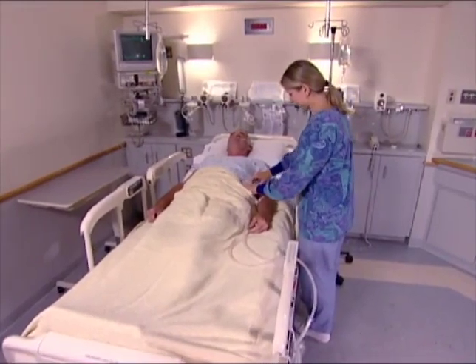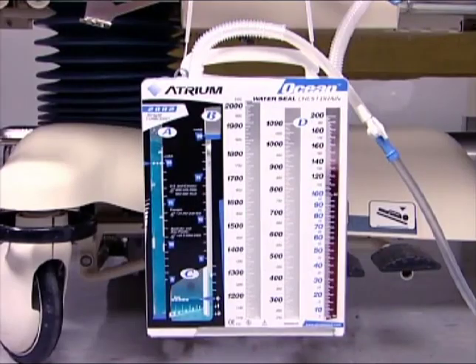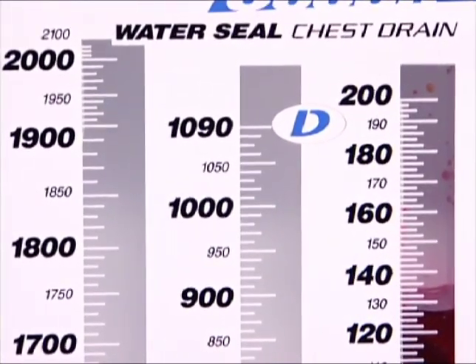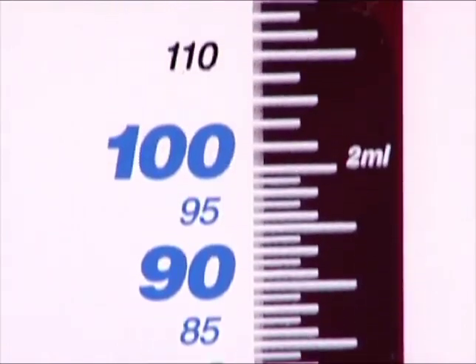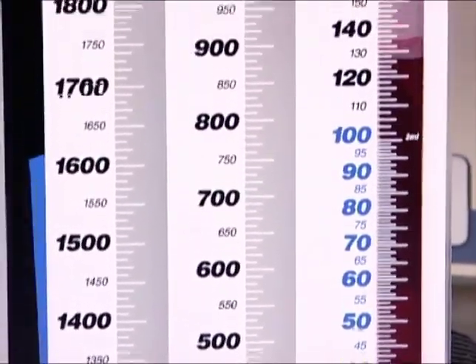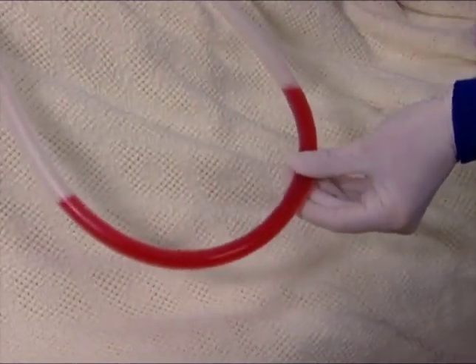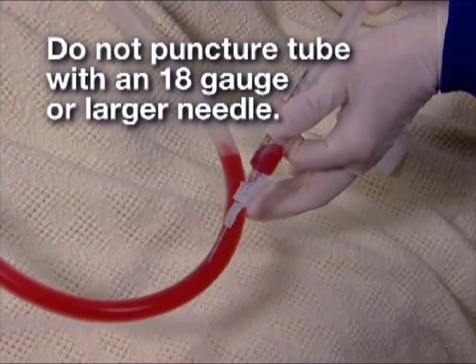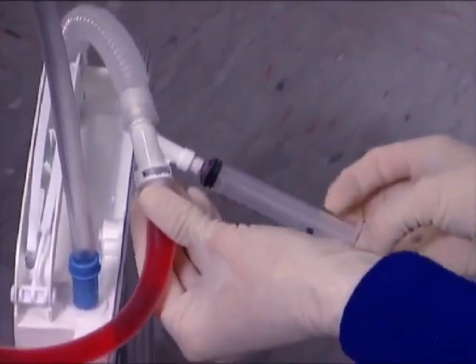All patient tubes and suction connections should be routinely checked to ensure proper leak-proof operation and chest tube patency. The Ocean 2002 Single Drain Collection Chamber incorporates a large writing surface with big, bold numbers and easy-to-read fluid level graduations. The first collection chamber column is calibrated in small 1 mL increments up to 100 mL, then in 2 mL increments up to 200 mL. Subsequent collection chamber columns are calibrated in 10 mL increments up to the maximum drain capacity of 2100 mL. Samples of drainage fluid can be taken directly from the patient tube, or on selected models, from the needleless luer lock sampling port located on the patient tube connector.